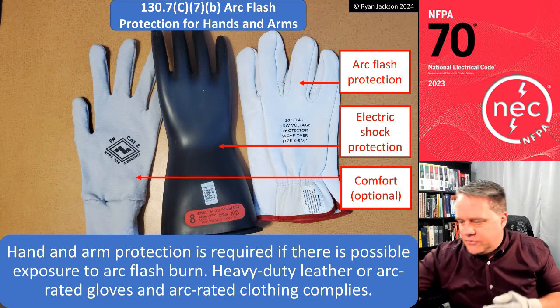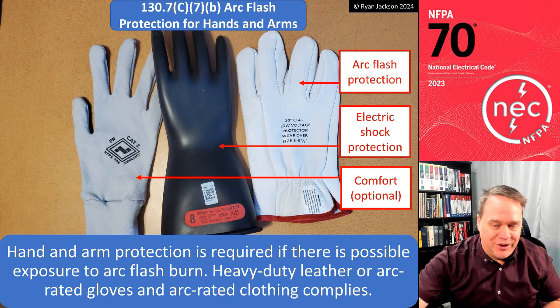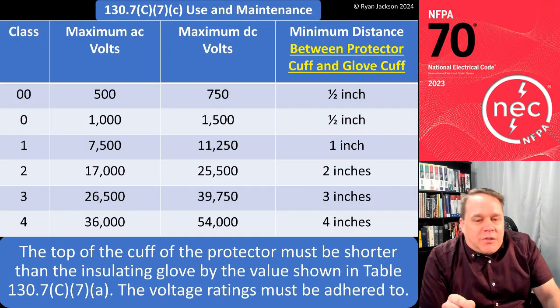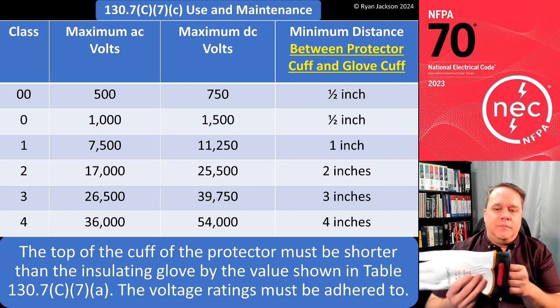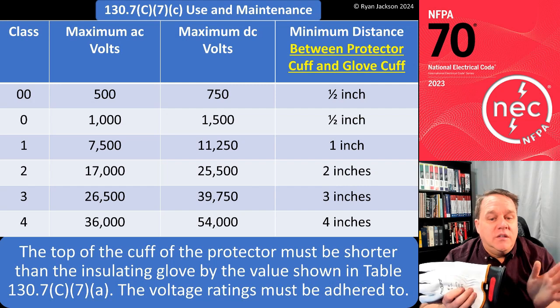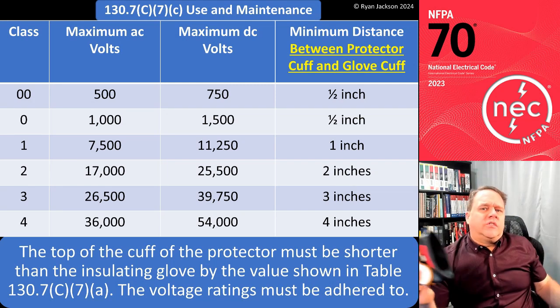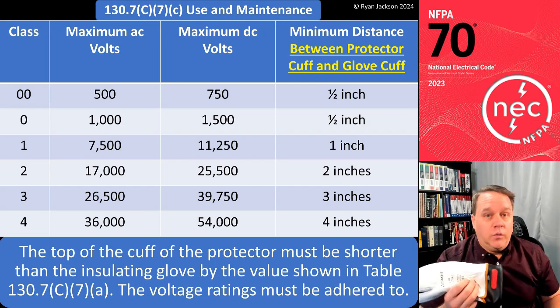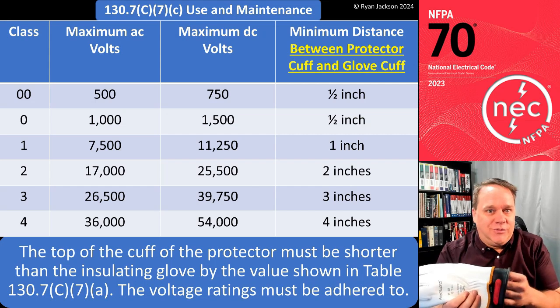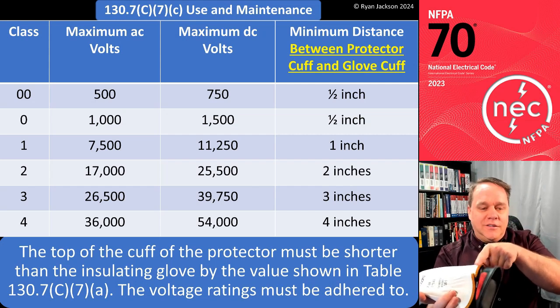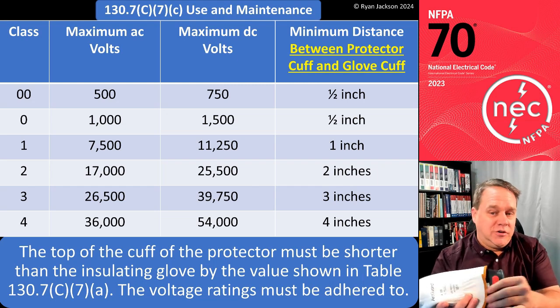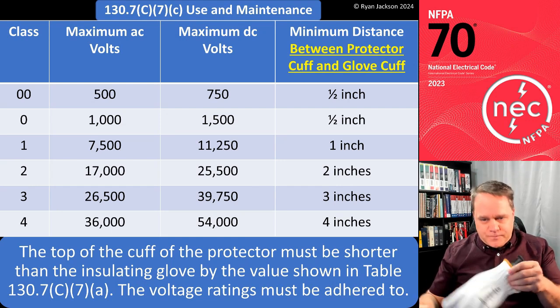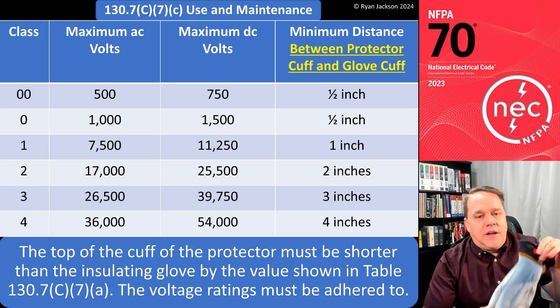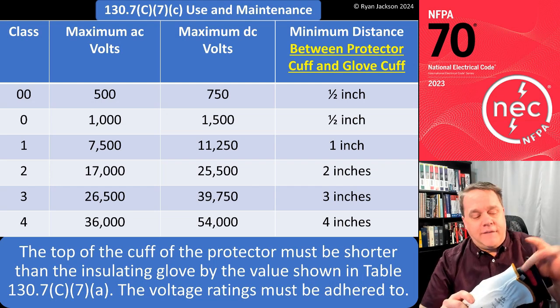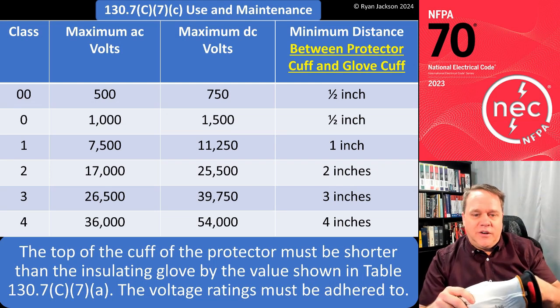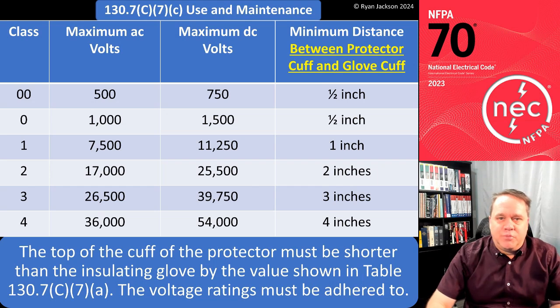So make sure you got your gloves. Make sure you have your protectors over them. I almost said leather protectors. Top of the cuff of the protector must be shorter than the insulating glove by the value shown in table 130.7 C7A, and the voltage ratings must be adhered to. What it used to say is the length of the gauntlet. Okay, what does that mean? Well, I don't know what a gauntlet is, right? I'm a dumb electrician. What's a gauntlet? Distance from the protector to the glove, all right? Has to be not less than the value shown in the table. And you can see it's 1 inch. Well, it's 1/2 inch for category double aught and 0 gloves, and that'll give you up to 1,000 volts, all right, so 1/2 inch. Once you get a little bit higher than that, it's 1 inches, and it gets bigger the higher the voltage you get, which is pretty predictable.